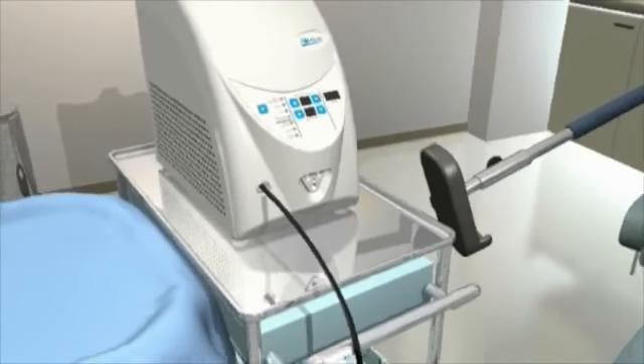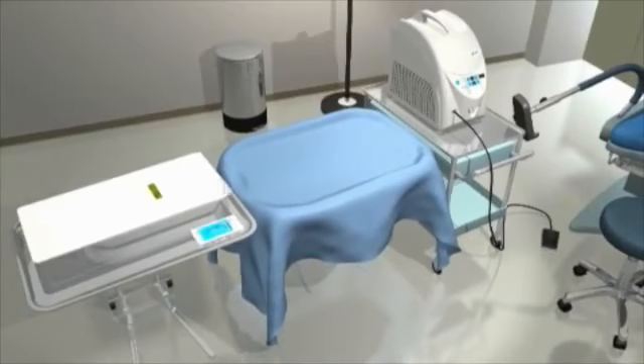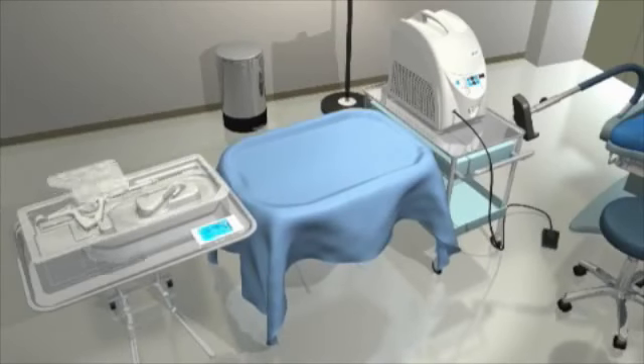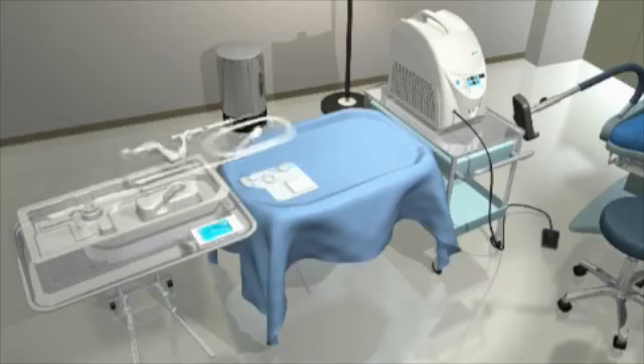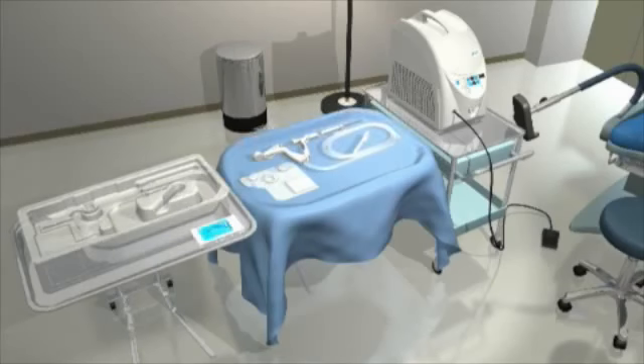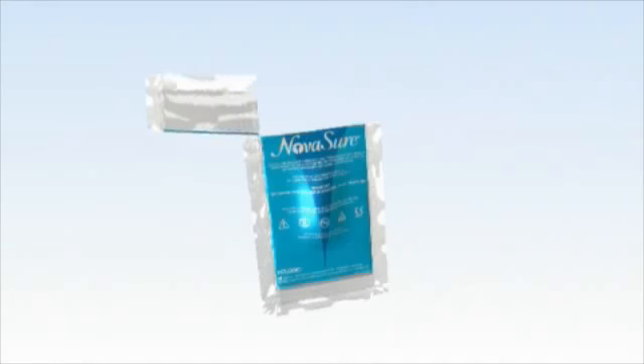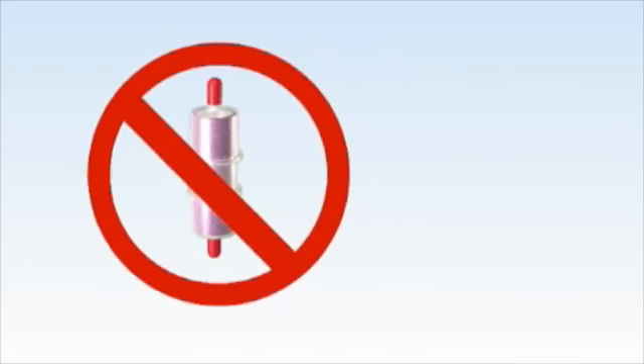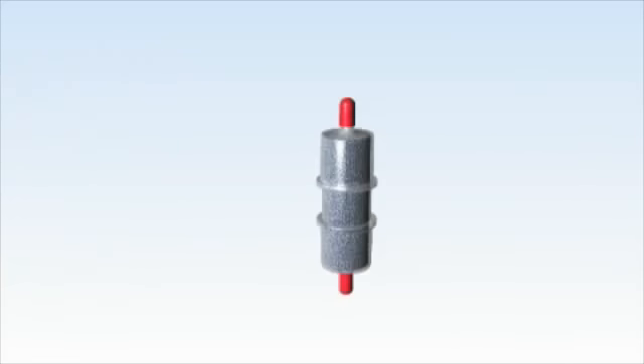Open the sterile NovaSure device package. Place the disposable device with the connecting cord into the sterile field while being careful to keep the non-sterile suction line desiccant pouch out of the sterile field. Open the non-sterile suction line desiccant pouch. If the suction line desiccant is pink, replace the desiccant prior to initiating the ablation procedure.